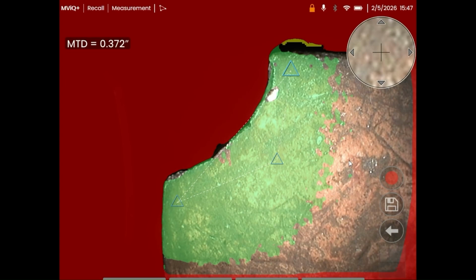The measurement plane is not a measurement itself. Instead, it creates a mathematically defined 3D flat surface based on 3 user-placed points. Once set, it extends beyond the physical edges of the part, allows cursor placement in red, no data pixels, and projects measurement cursors onto a clean, stable surface, greatly improving measurement performance on flat features.